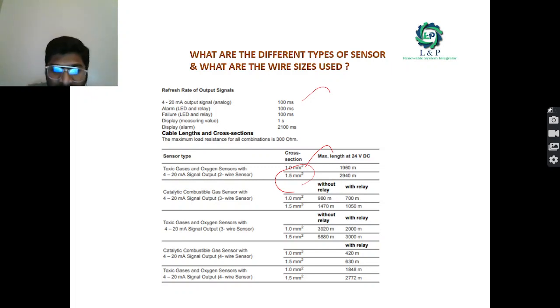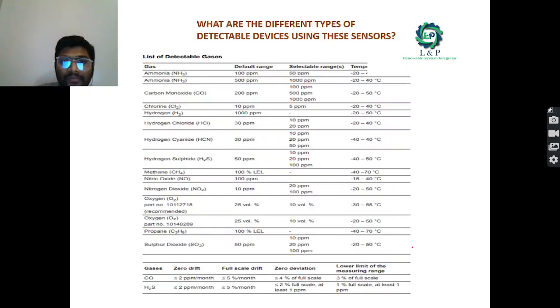If you're going for 4-wire sensors with a 1 square mm cable, with relay you can go up to 420 meters. If you're going for a 1.5 square mm cable, you can use it up to 630 meters.